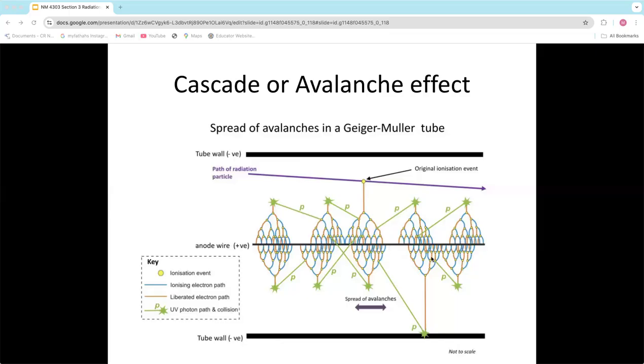Now, there's one other kind of reaction that occurs during this. Everything traveling toward the anode is the electrons, and they're creating the reactions. But remember, the ion pairs are pulled towards the cathode, and that's the wall of the tube in most of these. When that ion pair strikes the cathode, or the wall of the tube, another reaction is created. In this case, it doesn't have an ionization reaction. It doesn't kick off an electron. But what it does is excite the cathode.